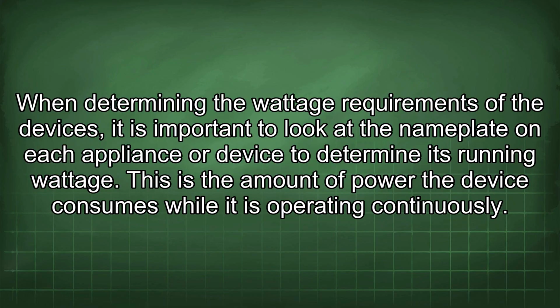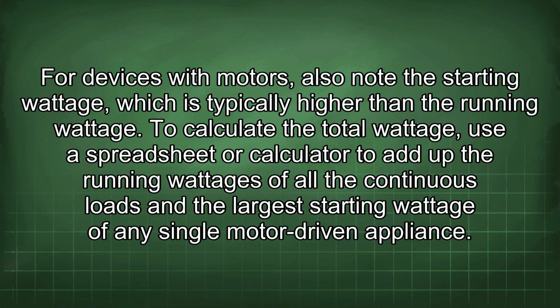When determining the wattage requirements of the devices, it is important to look at the nameplate on each appliance or device to determine its running wattage. This is the amount of power the device consumes while it is operating continuously. For devices with motors, also note the starting wattage, which is typically higher than the running wattage. To calculate the total wattage, use a spreadsheet or calculator to add up the running wattages of all the continuous loads and the largest starting wattage of any single motor-driven appliance.